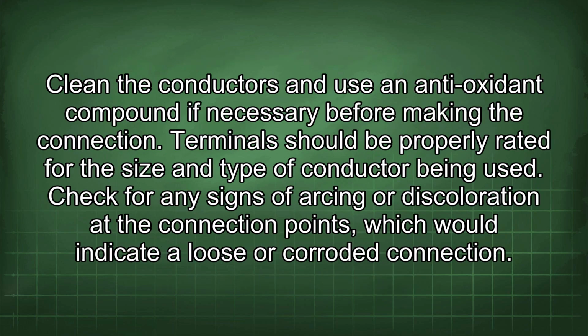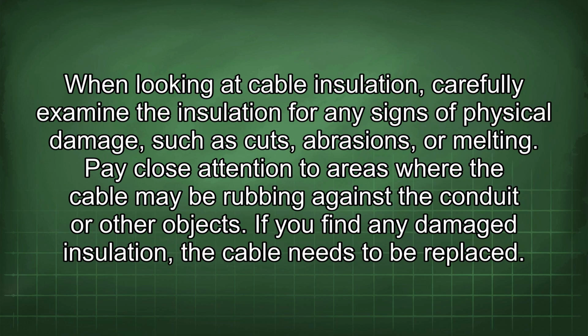Clean the conductors and use an antioxidant compound if necessary before making the connection. Terminals should be properly rated for the size and type of conductor being used. Check for any signs of arcing or discoloration at the connection points, which would indicate a loose or corroded connection. When looking at cable insulation, carefully examine the insulation for any signs of physical damage, such as cuts, abrasions, or melting. Pay close attention to areas where the cable may be rubbing against the conduit or other objects. If you find any damaged insulation, the cable needs to be replaced.